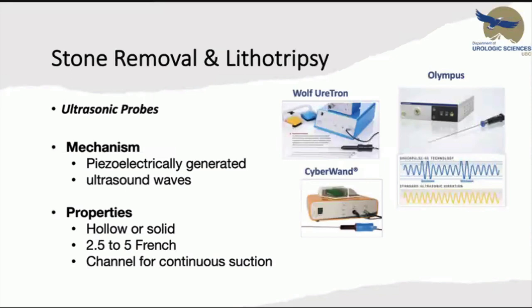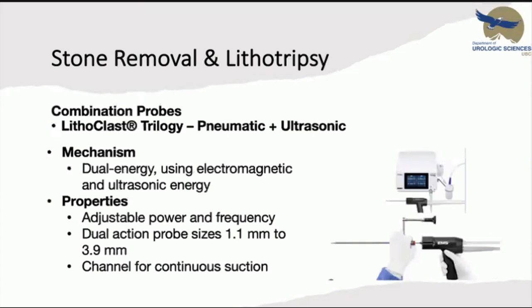Ultrasonic probes use piezoelectrically generated ultrasound waves and have a channel for continuous suction, with 2.5 to 5 French probes available. The combination probe — the Trilogy from Lithoclast — has both pneumatic and ultrasonic capability with dual energy using electromagnetic and ultrasonic energy, adjustable power and frequency, probe sizes ranging from 1.1 mm to 3.9 mm, and a channel for continuous suction.